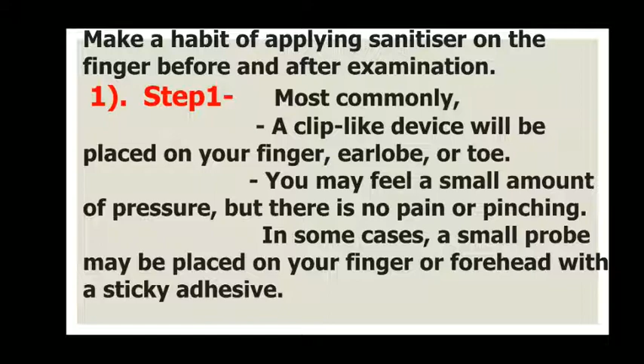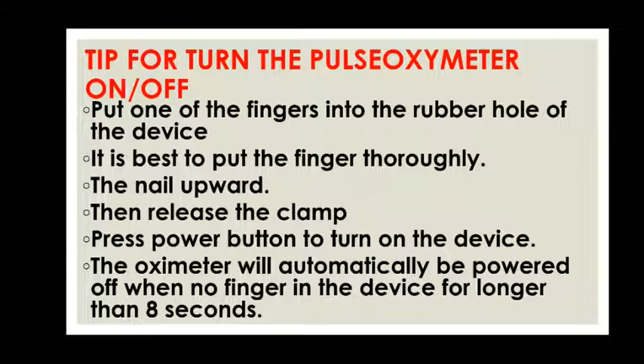So here is a tip for turning the pulse oximeter on and off. Put one of the fingers into the rubber hole of the device. It is best to put the finger in thoroughly, with the nail upward. Then release the clamp. Press the power button to turn on the device. The oximeter will automatically be powered off when there is no finger in the device for longer than 8 seconds.